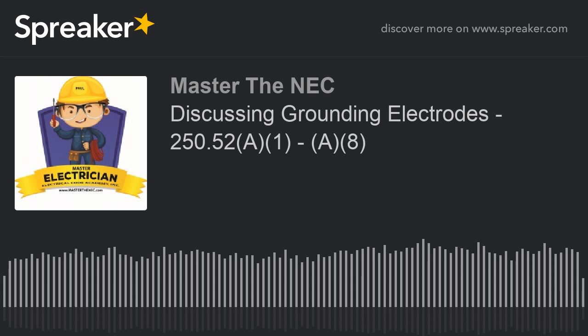Now, bonding jumpers. I kind of alluded to it when tying rod to rod together. It says bonding jumpers used to connect grounding electrodes together to form the grounding electrode system shall be installed in accordance with 250.64(A), (B), and (E), and shall be sized in accordance with 250.66. Because it says that, and doesn't say Table 250.66, that's how we were able to say that if we have two ground rods, we can use 250.66(A), which requires it not to be larger than a 6 copper or 4 aluminum.